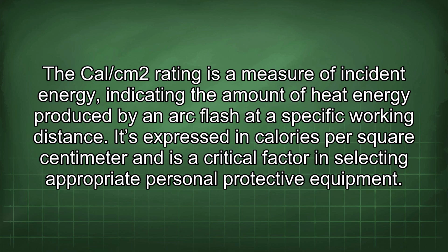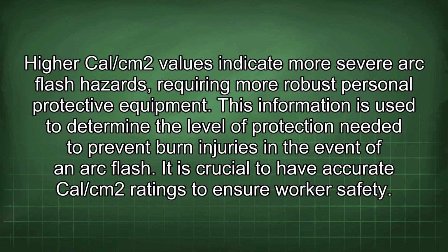The Cal/cm2 rating is a measure of incident energy, indicating the amount of heat energy produced by an arc flash at a specific working distance. It's expressed in calories per square centimeter and is a critical factor in selecting appropriate personal protective equipment. High Cal/cm2 values indicate more severe arc flash hazards requiring more robust personal protective equipment. This information is used to determine the level of protection needed to prevent burn injuries in the event of an arc flash. It is crucial to have accurate Cal/cm2 ratings to ensure worker safety.